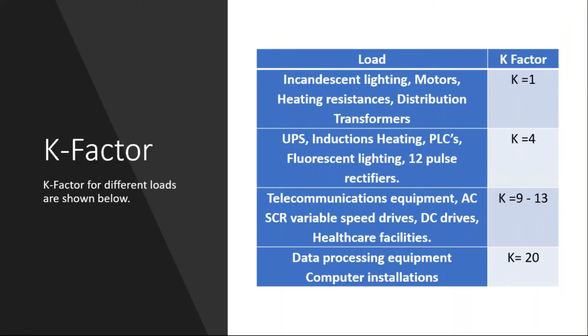Say, for example, if a load is a motor, then the K factor is just 1. It is nothing special. But if you are using a transformer for induction heating applications, normally the K factor will be somewhere close to 4. If a customer has the harmonic information, then this K factor can be calculated, whether it is more or less, and the design can be accurate to the specification requirement. This is very, very tricky: if the K factor is not clearly specified, then your transformer cost can go up quite a bit. And if it is under-specified, then it will be a problem in the field, because you cannot cool for the additional harmonic loading requirement. So these two are very important for the specification to include.